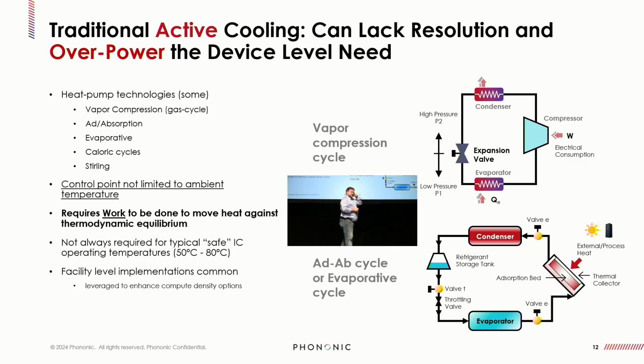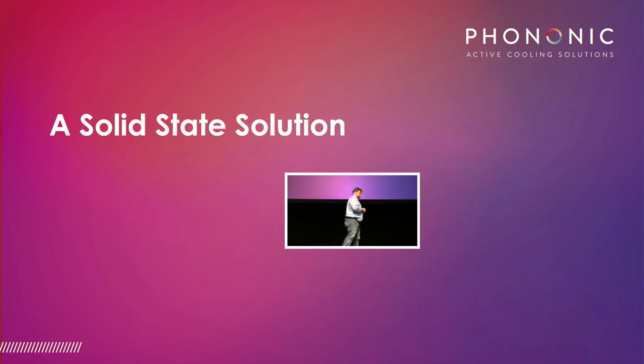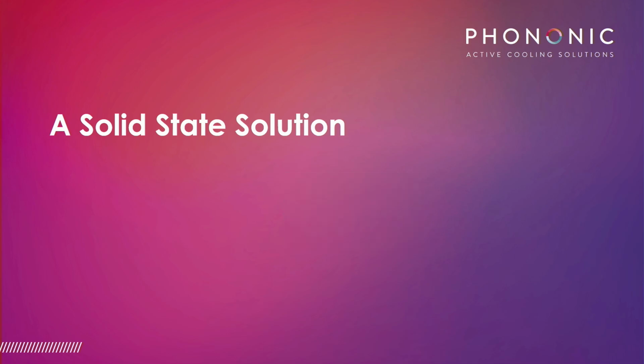What I mean by that is typically a device has a variable load, and if you design a system to manage a maximum load, you will tend to overcool. That could be very bad in a system where you don't want free water condensation to form. So effectively you are overpowering that system and you don't have the resolution you need to be finely controlled and responsive to the actual cooling load. That said, there might be a way.